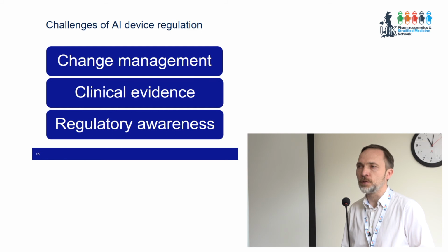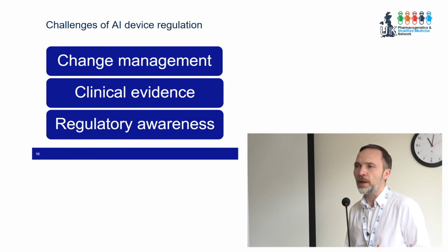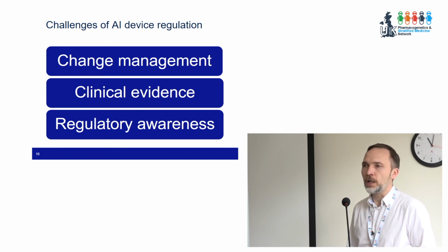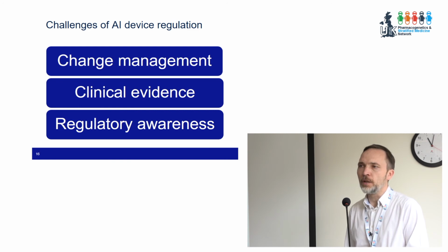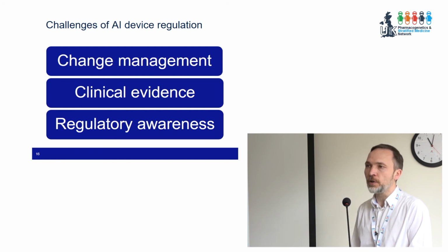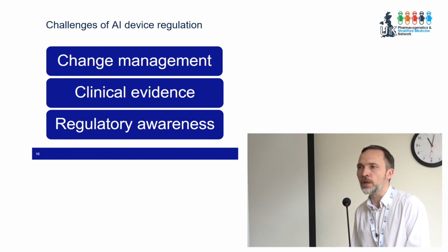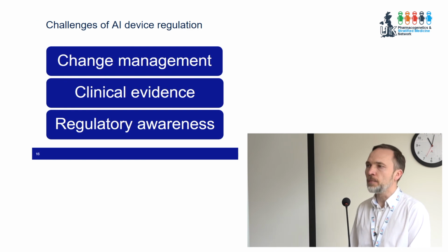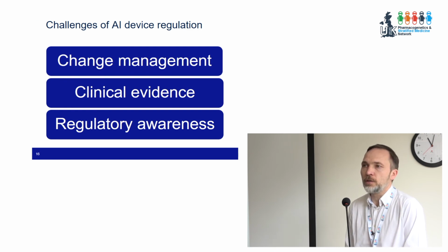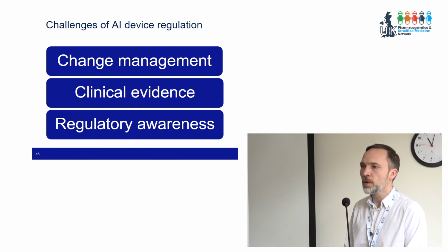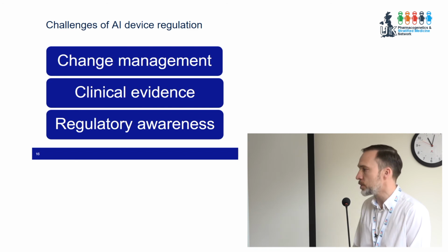Clinical evidence, we want to see the clinical evidence throughout the lifetime of the product. We also want to start thinking about what can you use to demonstrate that AI, that algorithm is okay? There's a lot of data out there, and there's a lot of patient-related data out there. As part of the Regulators Pioneer Fund, MHRA will be working to look at synthetic data sets to see if synthetic data sets can be used as part of validation of a medical device. That should be quite an interesting process because I believe it's not so difficult to produce a synthetic data set, but it might be difficult to open up all your patient registry information to commercial developers.